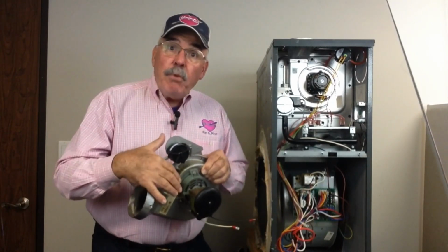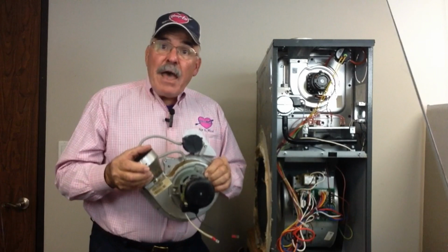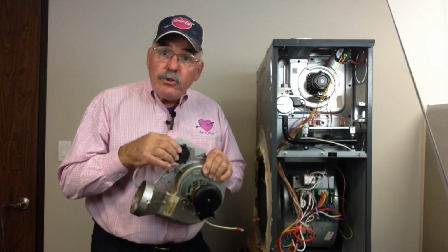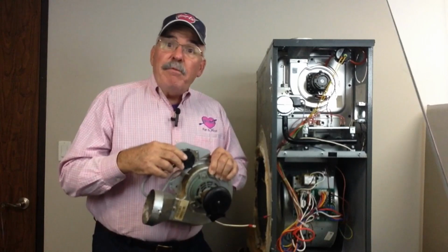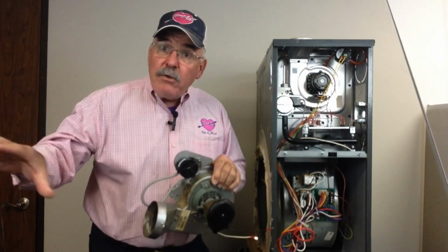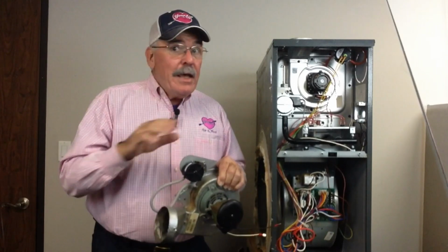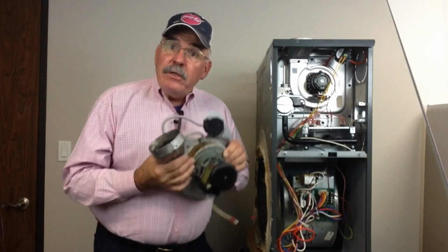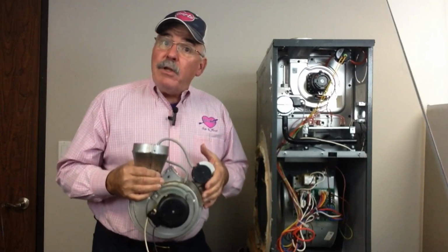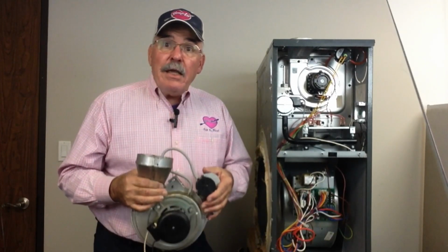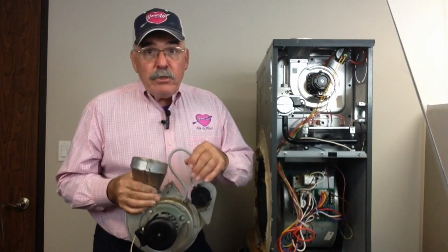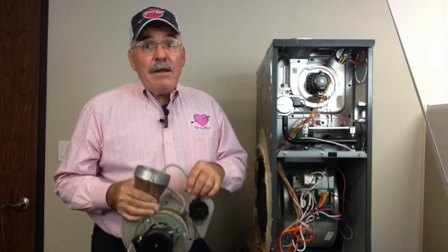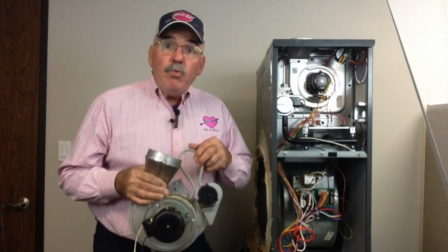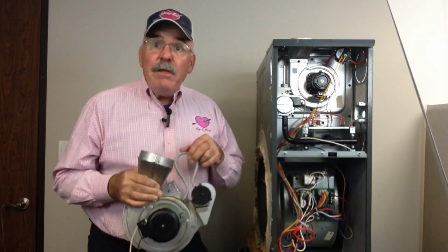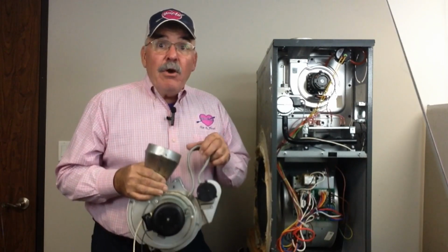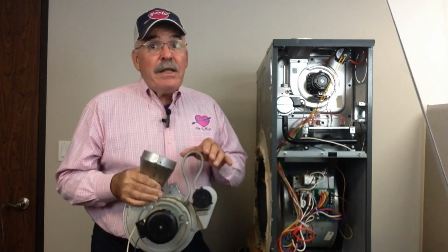Now if the hoses or the ports are stopped up, they won't allow vacuum pressure to come up here to the pressure switch, and this switch will not close. If this happens, an error message is going to be sent to the board that's going to shut this furnace down and no heat's going to be produced. Now if this type of shutdown occurs, the technician is going to have to come to your house and remove the assembly, then clean or replace it, and the vacuum tubes as well, to make sure that your furnace operates again and provides heat inside your home. Now this is one of those very crucial things that you positively must have inspected, cleaned, and maintained, or your furnace is going to leave you and your family sitting there and freezing.